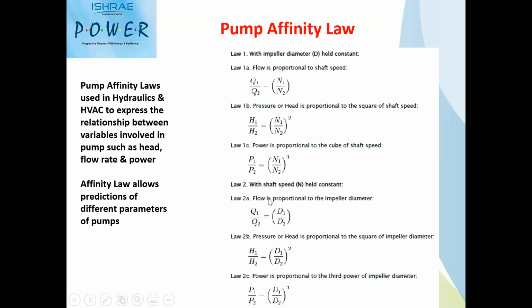Similarly, in the case of a constant speed application where your RPM is constant, you can vary the diameter of the impeller, and how the diameter of the pump is related to your flow, head, as well as your power is defined in this affinity law. So whenever you want to do calculations for variable speed or variable impeller diameter with respect to your flow, head, and power, this is the basic typical affinity law which comes into the picture for all the calculations.